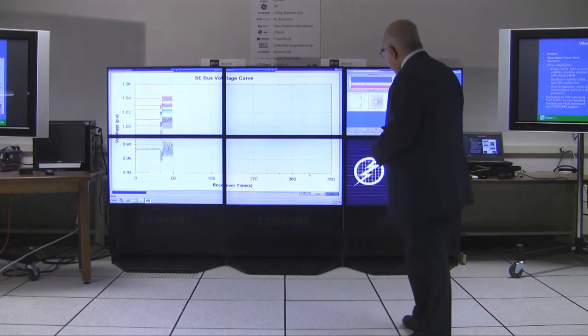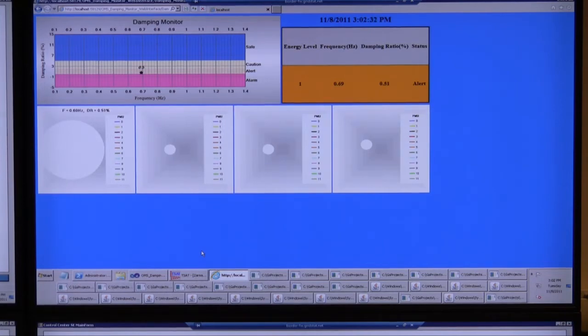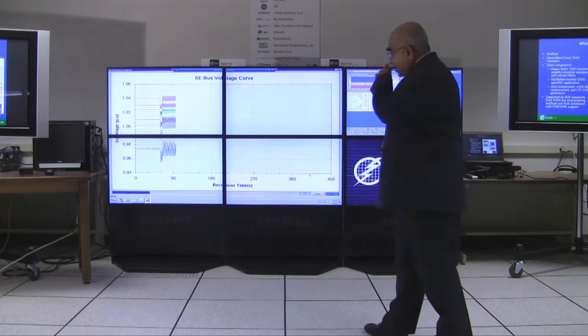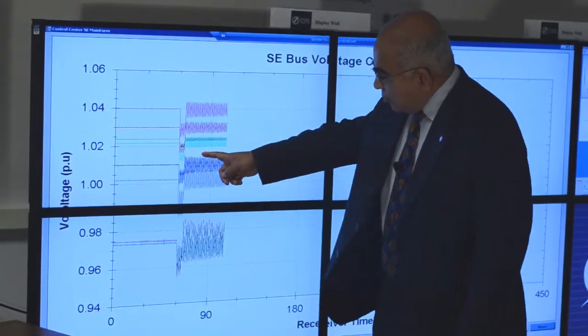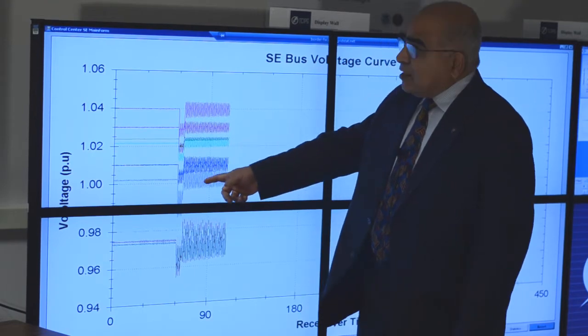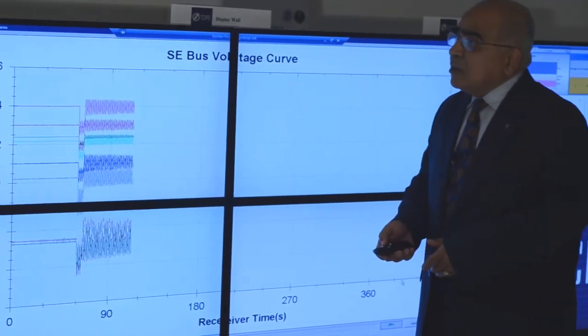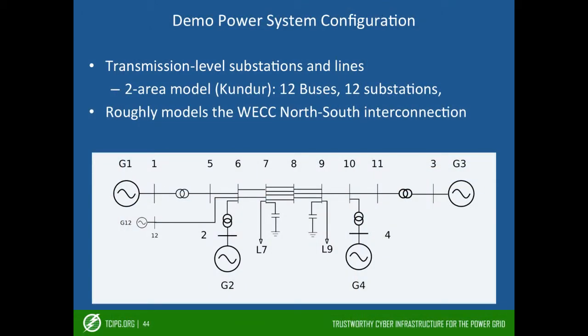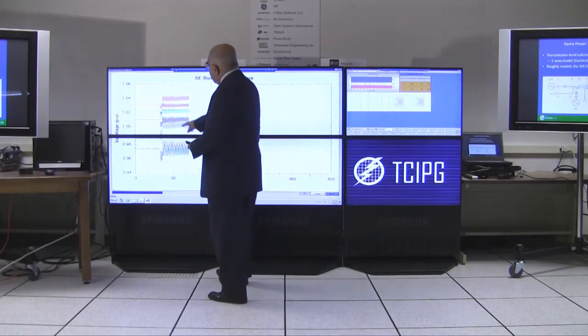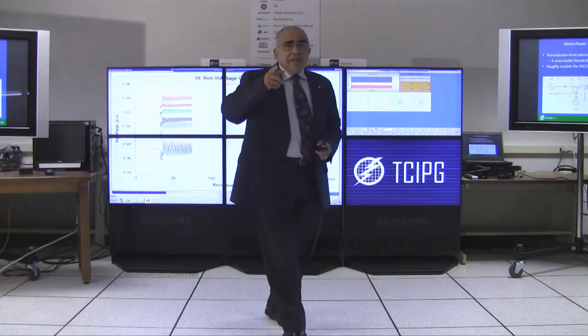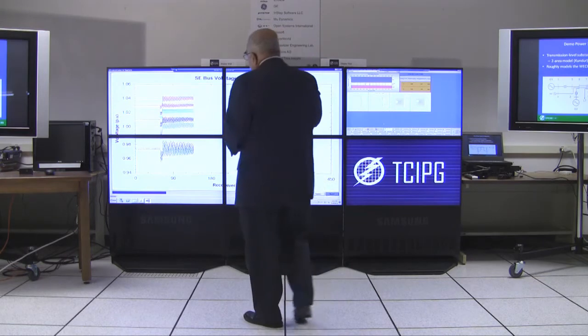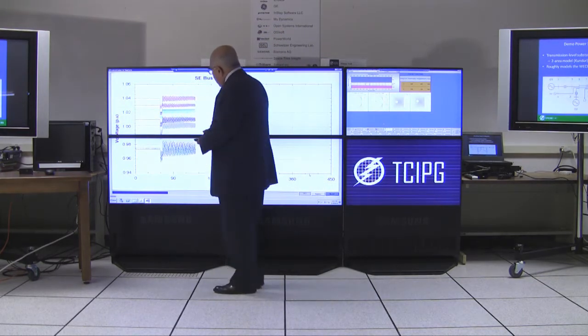On this display we have the oscillation monitor and the bus voltage state estimator. The simulation started at zero time and has gone about one minute in. There was an event shown on this diagram — this particular line in the power system was opened and then closed. Everything is coming back to normal, and the state estimator has taken data produced at five times a second to give the voltages.